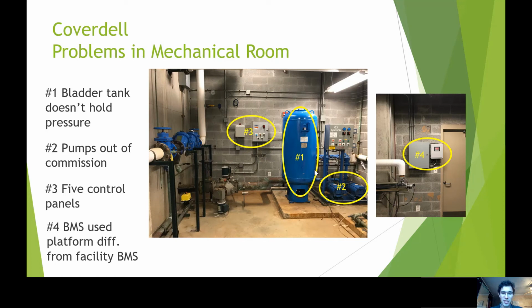And it's an interesting dilemma, because even if you were to get the pumps working, the bladder tank doesn't work, and there are some other components in the system that are not communicating right with each other. So even if you got the pumps to work, you couldn't get the whole system to work. So it's important to think about rainwater systems as a collection of parts that are interdependent on each other. In addition, there are 5 control panels, one of which doesn't do anything anymore, and 2 others aren't labeled, so they don't indicate their function. And as I mentioned before, the building management system used a different platform from the facility building management system.